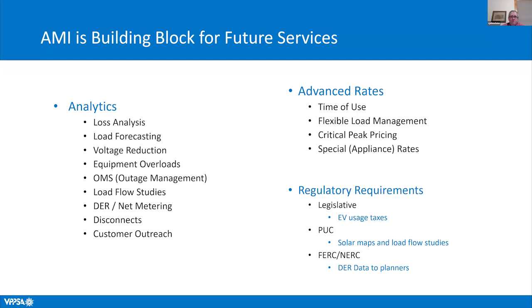One of the big things we see right off with this is potential equipment overloads. That's why we're pushing the GIS system so heavily, because we can tie the CIS information and the 15-minute usage data to the maps and get a visual picture of the load on a particular transformer, the load on the line, and identify transformer overloads or underloads. There was, with the transformer shortage, actually a Massachusetts utility last year that used this technology to look.